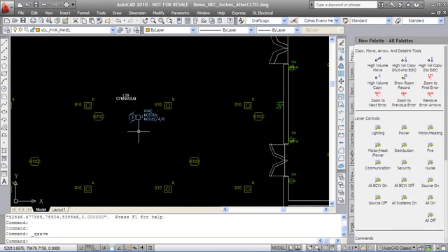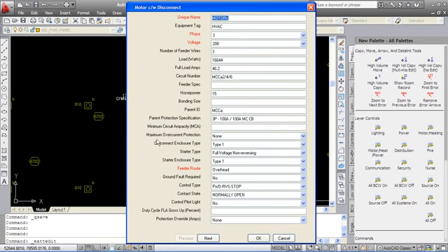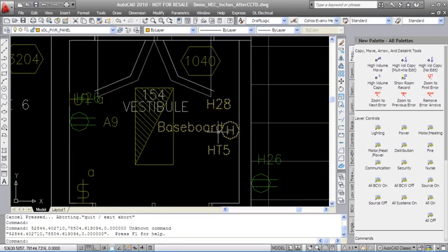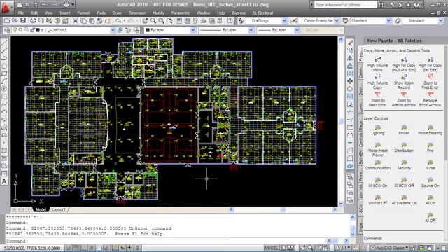Automated circuiting also circuits motors in compliance with your request whether to service them at the MDP, the MCC, or branch circuit panel based on their size. The protection is selected based on CEC and NEC standards, and the feeder will get automatically selected later when we run any report that depends on it, like panel schedules or the single line diagram. Heaters too are automatically circuited.